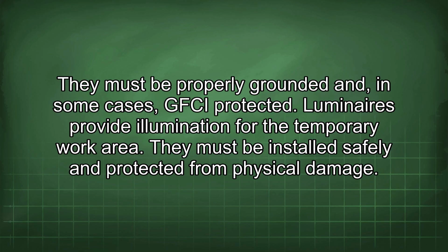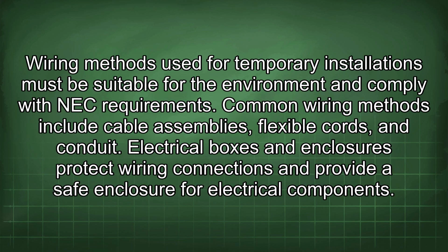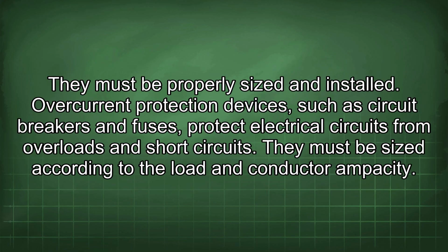Luminaires provide illumination for the temporary work area. They must be installed safely and protected from physical damage. Wiring methods used for temporary installations must be suitable for the environment and comply with NEC requirements. Common wiring methods include cable assemblies, flexible cords, and conduit. The electrical boxes and enclosures protect wiring connections and provide a safe enclosure for electrical components. They must be properly sized and installed.